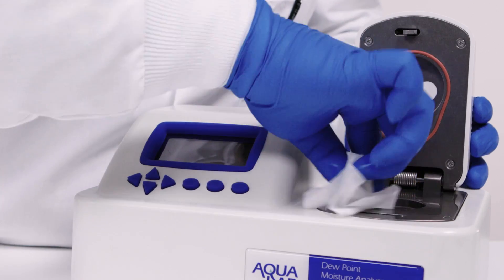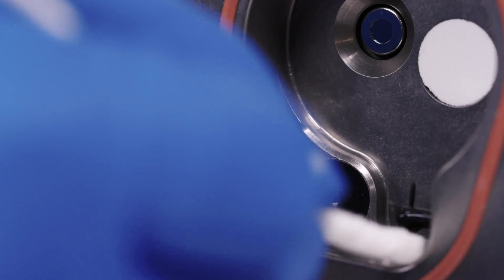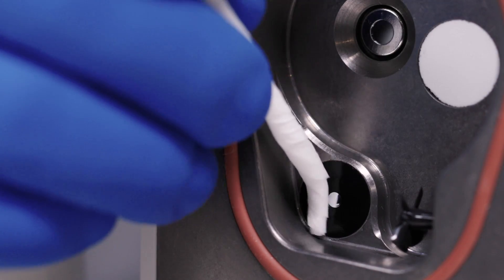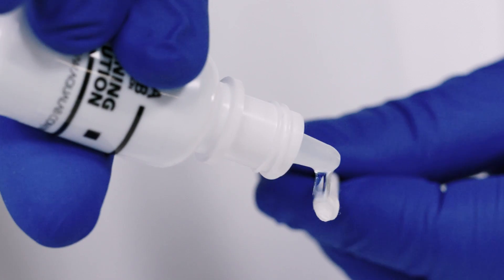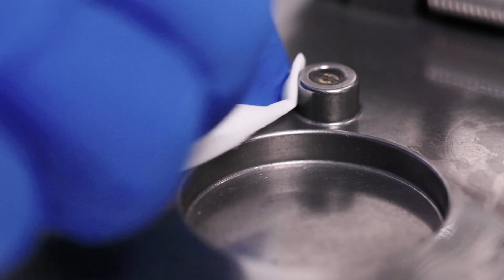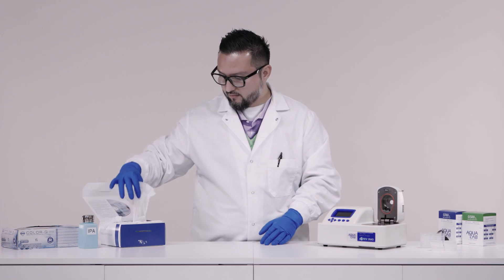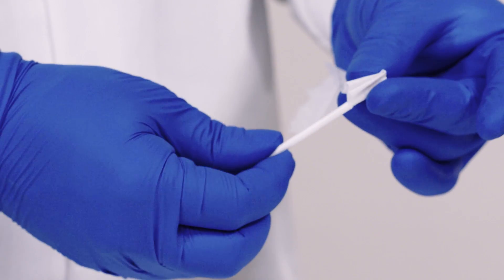To review, wash, rinse, and dry the sample chamber surface area. Wash, rinse, and dry around the fan and sensors. And wash, rinse, and dry each of the three sensors. Washing with isopropyl alcohol or Aqualab cleaning solution helps break down contaminants. The rinsing step washes away the contaminants, and the drying step leaves the surface clean and dry. Change kimwipes frequently to make sure that you don't cross contaminate surfaces inside the chamber.